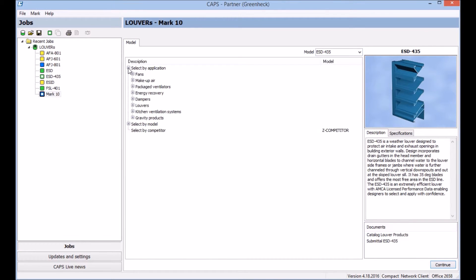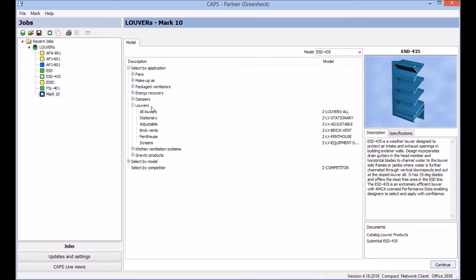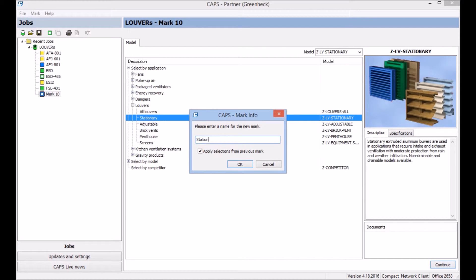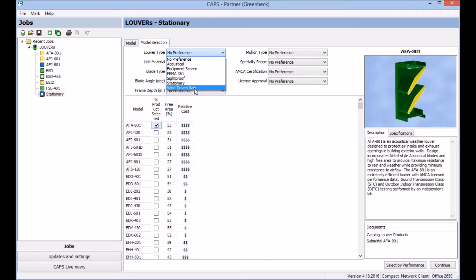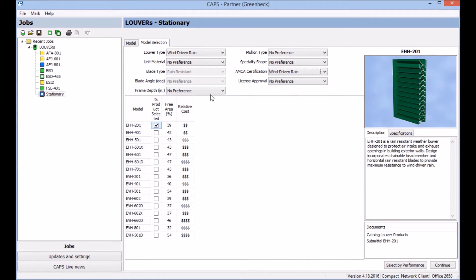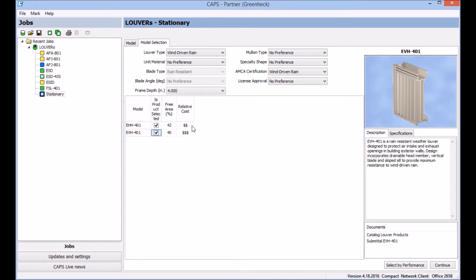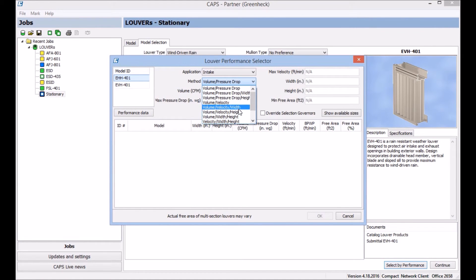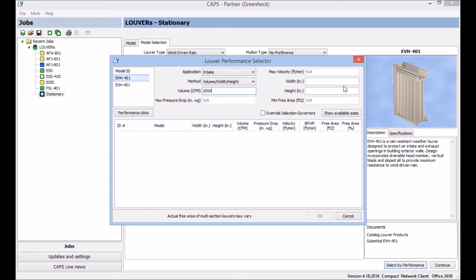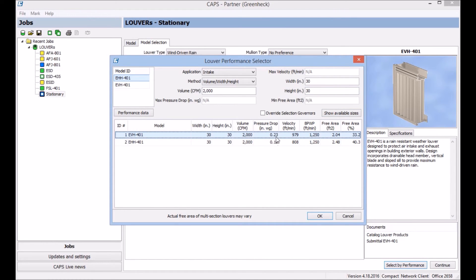For this other model, I don't know exactly what model I want, but I know it's for a data center and I don't want any water getting in this louver. So I'm going to go to louvers, stationary, double click. I know the louver type needs to meet wind-driven rain, it needs to have that AMCA certification, and I know the frame depth has to be four inches. Now I'm left with two different models: the horizontal blade and the vertical blade. I'm going to select them both. I can see the free areas are a little different and the costs are a little different. Selecting by performance again — it's an intake — I'll enter volume, width, and height at 2000 CFM. I'm going to go a little bit larger since I know my free area is smaller on these than my last louver. Clicking show available sizes, I can now compare both models. The pressure drop on the horizontal blade is half as much as the pressure drop on the vertical blade.